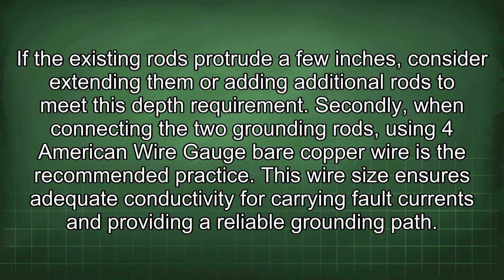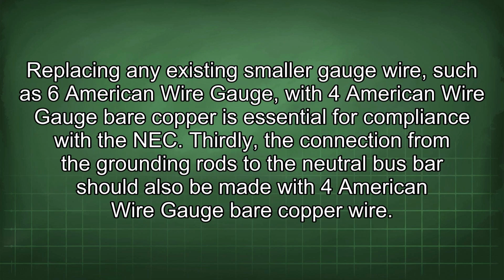Secondly, when connecting the 2 grounding rods, using 4 American wire gauge bare copper wire is the recommended practice. This wire size ensures adequate conductivity for carrying fault currents and providing a reliable grounding path. Replacing any existing smaller gauge wire, such as 6 American wire gauge, with 4 American wire gauge bare copper is essential for compliance with the NEC.